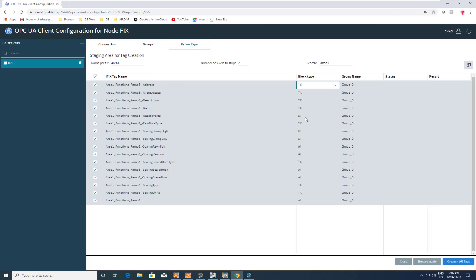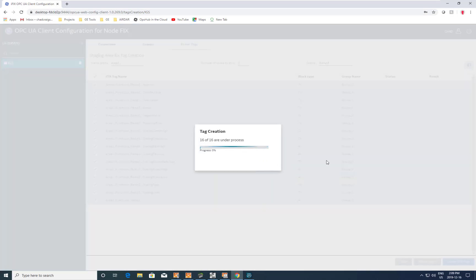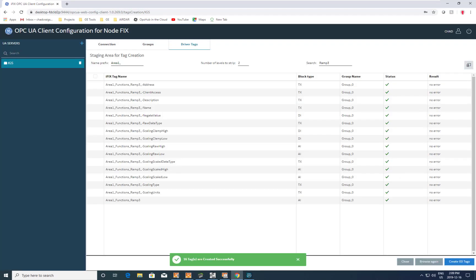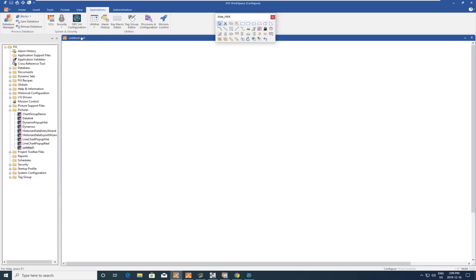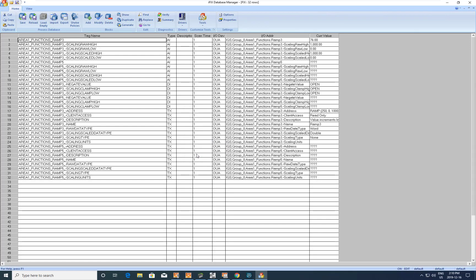We pick up their block types and can potentially change those if we wanted something different, but we'll take the defaults. We hit create tags, and this goes out to iFix and starts creating those tags in the iFix tag database. Those tags were created successfully. If we go take a look at those tags in the database, we will see that they're created and they're talking. We've connected to the IGS OPC UA server from the iFix OPC UA client and created valid tags in iFix to communicate with it.